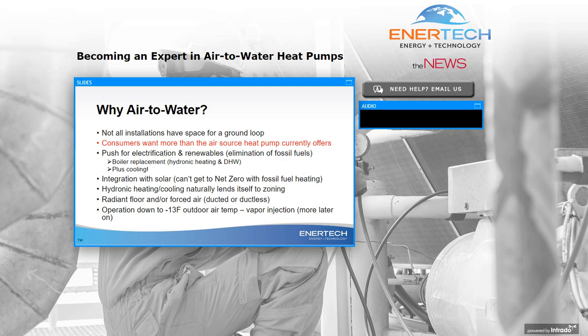So why air to water? Let's just even look at that from a perspective of complete efficiency and performance. So not all installations have an opportunity for a ground loop. Many of the urban markets, there's just no opportunity to achieve maximum efficiency, performance, and comfort. But yet we also highlight on your second bullet point, customers want more than just what an air source heat pump offers. Even though they're incredible efficiencies, they still don't have the ability to address domestic hot water. And you'll see that coming up shortly.